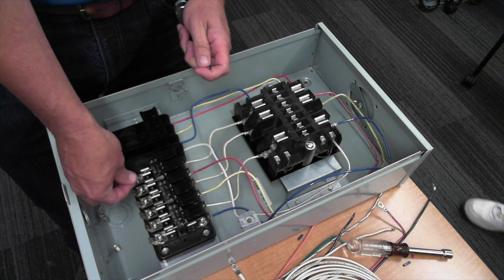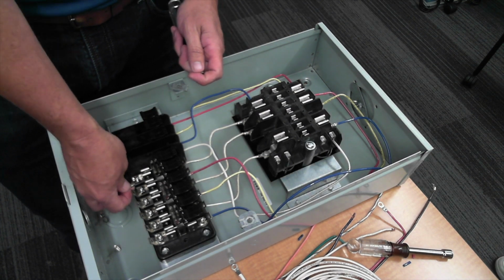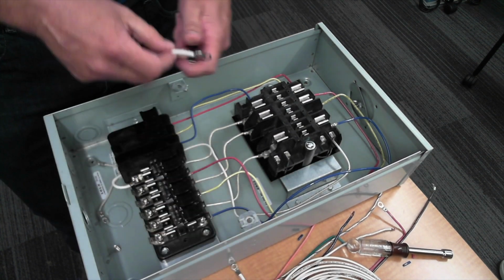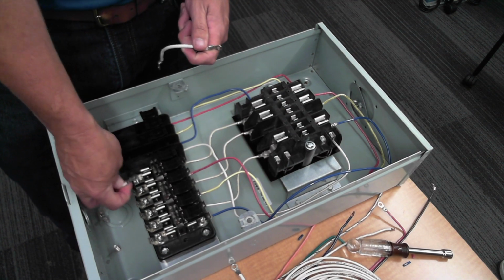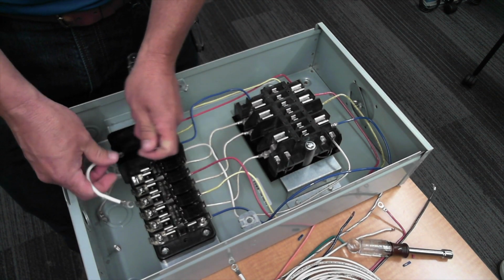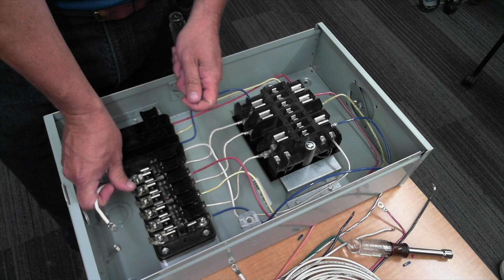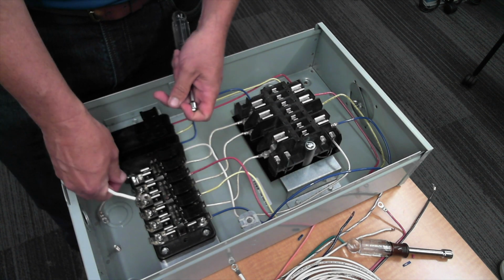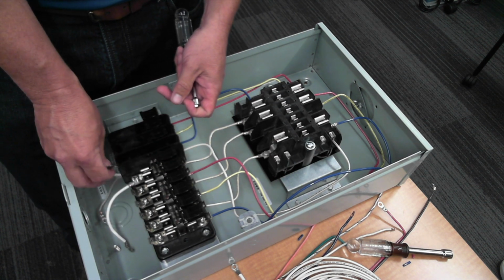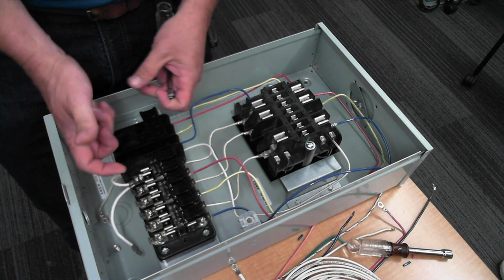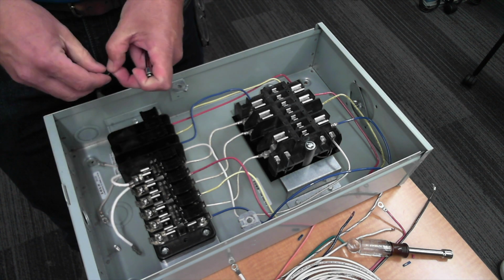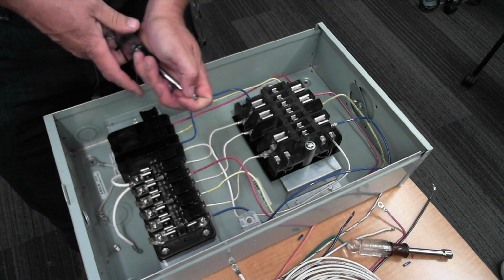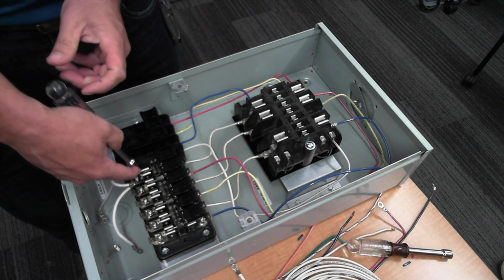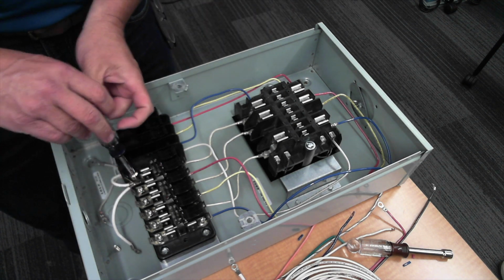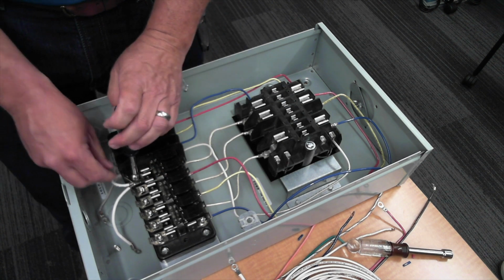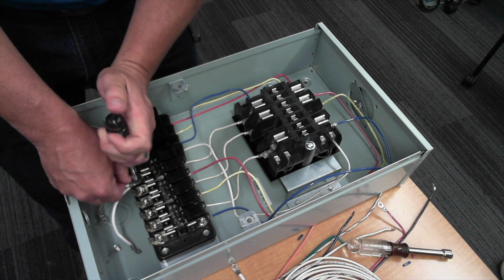So on this one, we'll have that one going there, and then we will put another one — I found out in the past it's best to put one terminal upside down, so to say, so it'll fit in there. Then you put your other one like that, and then you can put that on there. So you're not stacking the crimps on top of one another, because if you stack the crimps up there, you start running out of room. You have to turn crimp outside, crimp outside.